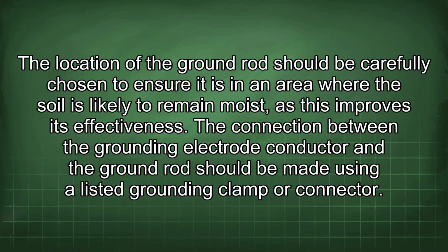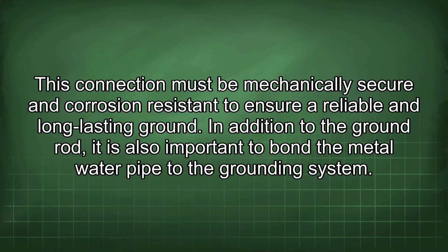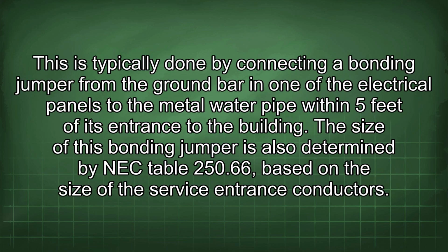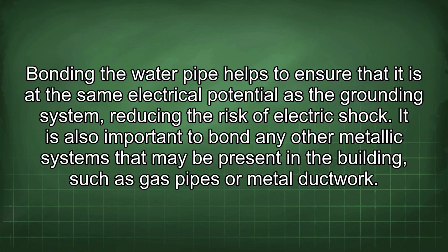The connection between the grounding electrode conductor and the ground rod should be made using a listed grounding clamp or connector. This connection must be mechanically secure and corrosion resistant to ensure a reliable and long-lasting ground. In addition to the ground rod, it is also important to bond the metal water pipe to the grounding system. This is typically done by connecting a bonding jumper from the ground bar in one of the electrical panels to the metal water pipe within 5 feet of its entrance to the building. The size of this bonding jumper is also determined by NEC Table 250.66 based on the size of the service entrance conductors. Bonding the water pipe helps to ensure that it is at the same electrical potential as the grounding system, reducing the risk of electric shock.